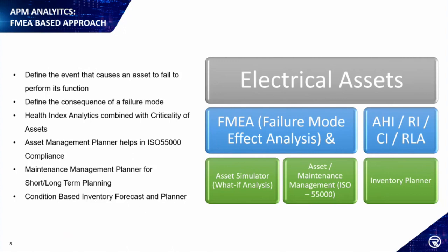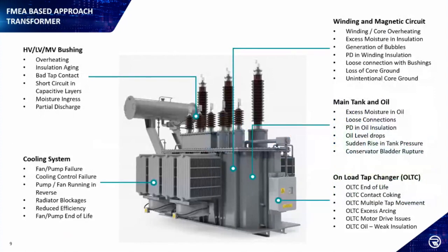So let me give you an example of a transformer. Typically, the main components of a transformer are bushings, cooling system, winding and magnetic circuit, main tank and oil, and OLTC. What you are seeing on the screen as a sub bullet point on each component is the typical failure mode of those components. If I talk about winding and magnetic circuit, typical failure modes are overheating related issues, excess moisture related issues, bubbling related issues, partial discharge related issues. That could be because of loose connections with the bushing or loss of core ground current, unintentional core ground. So these are the typical failure modes of the winding and magnetic circuit.